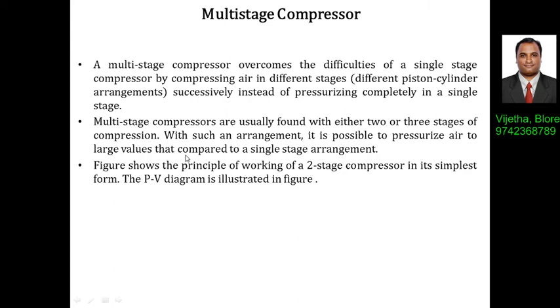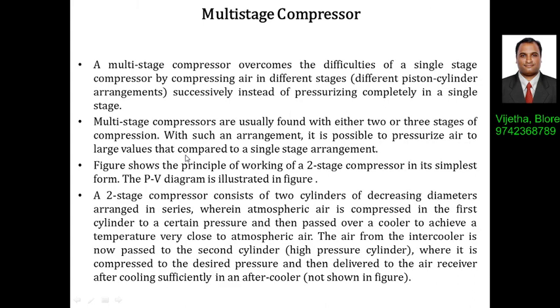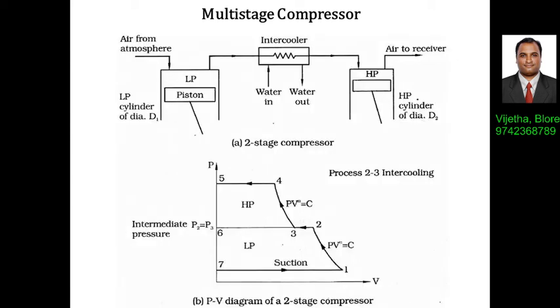The figure shows the principle of working of a two-stage compressor in its simplest form, and the PV diagram is also illustrated. A two-stage compressor consists of two cylinders decreasing in diameter arranged in series. Atmospheric air is compressed in the first cylinder to a certain pressure, then passed over a cooler to achieve temperature very close to atmospheric. The air from the intercooler is then passed to the second cylinder — the high-pressure cylinder — where it is compressed to the desired pressure and delivered to the air receiver after an after-cooler.